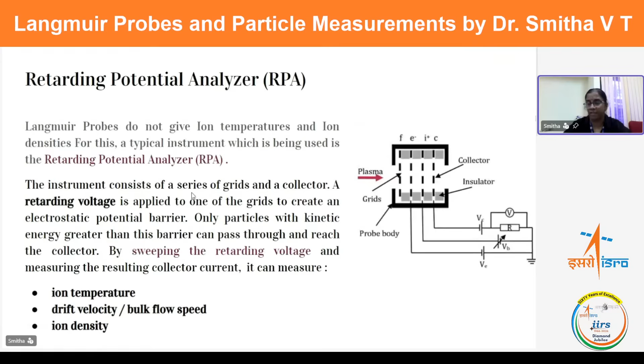Now, as I told, when we talk about very tenuous plasma, like the solar wind, or even in the magnetosphere, we talk about particle flux and energy. A Langmuir probe cannot be used to measure such plasma because it becomes so tenuous that the sheath becomes very large, and your Debye length becomes very, very large, meters and meters. Since the plasma or particle density is so low, the current becomes so small that it cannot be measured. So practical Langmuir probe measurements are not possible for such plasma.